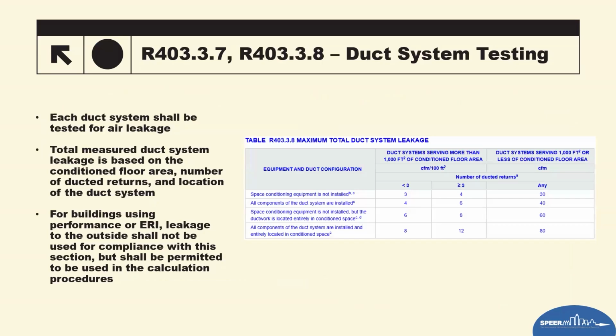Duct leakage allowance has changed considerably. It used to be much easier to say, well, it's 4 CFM per 100 square feet or 3 CFM per 100 square feet if the equipment isn't yet installed. Now there's a table to follow, and this table is based on multiple factors, including size of home, number of returns, and location of ductwork.